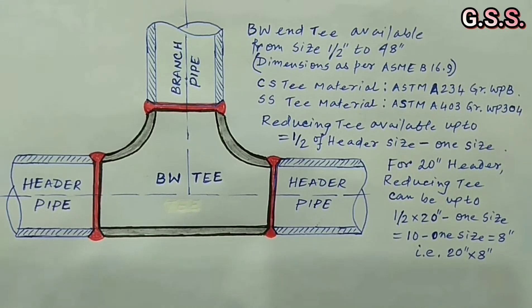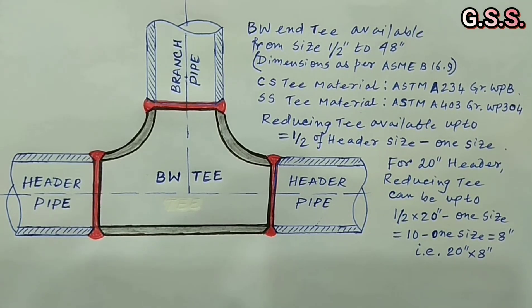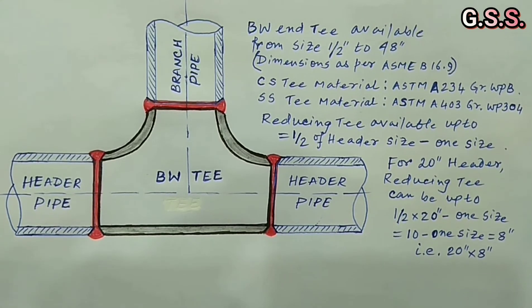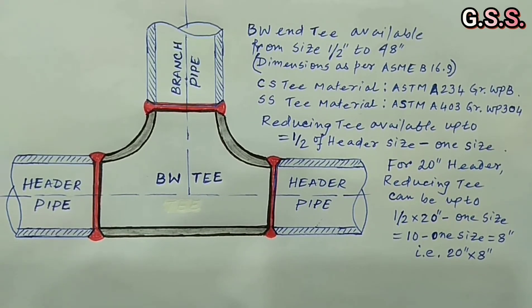If header pipe is of seamless construction, then T should be of seamless construction. If header pipe is of welded construction, then T should be of seamless type or welded type, that means pressed and welded type.